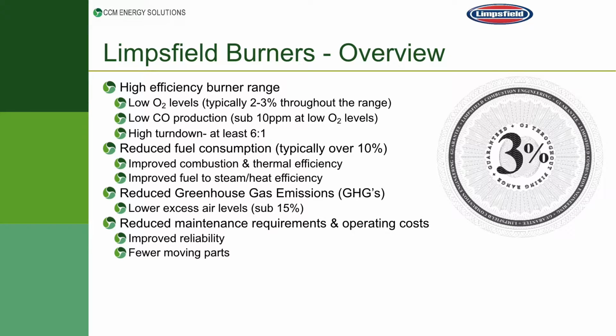When we look at the Limpsfield burners, when I go to a site and conduct my measurements, what I'm trying to look at on combustion efficiency is how well that existing setup is running at high fire, mid fire, and low fire. And typically on a site, the high fire oxygen levels will be 3 to 5%, which is okay. Once we start to modulate down to mid fire and down to low fire, those oxygen levels can go through to 7, 8%, and on some occasions 11, 12%, which is terrible.